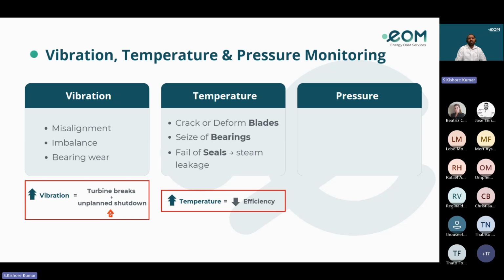Also, the steam temperature at inlet and outlet and the casing temperatures always have to be monitored, because the differential expansion in the turbine is affected by the change in the steam temperatures. So the casing temperatures give a further loading allowance and restrictions based on the temperatures in the steam turbine casing. And coming to the pressure monitoring.